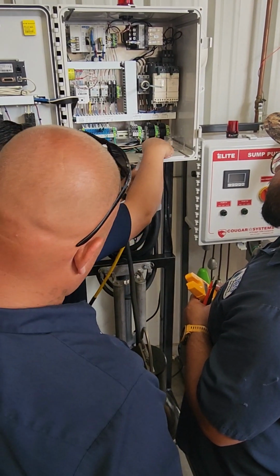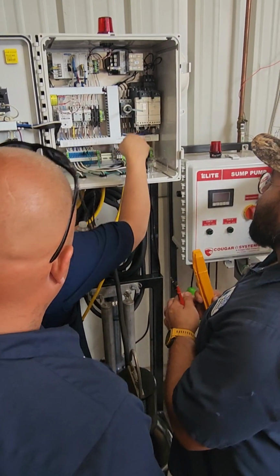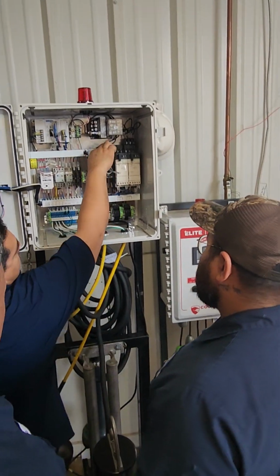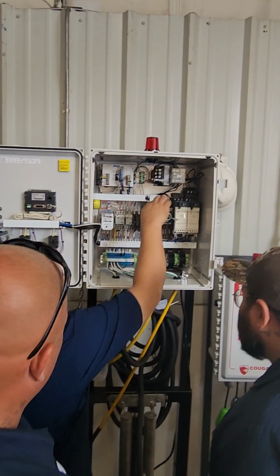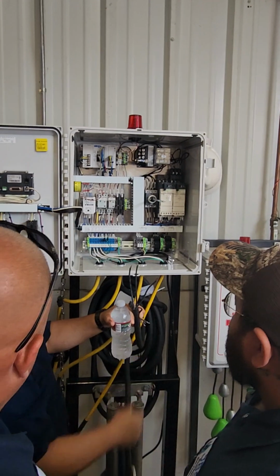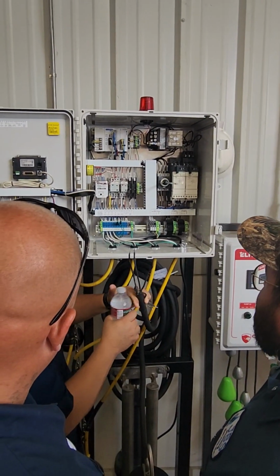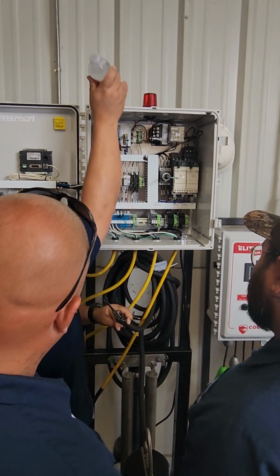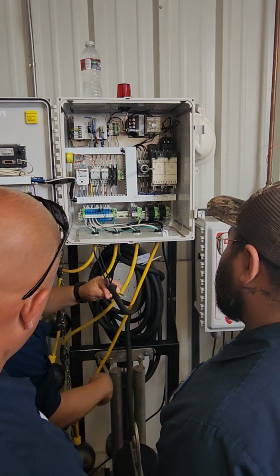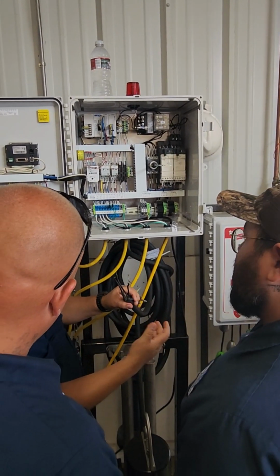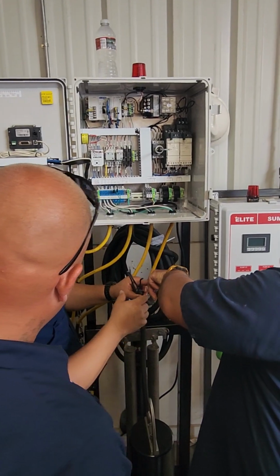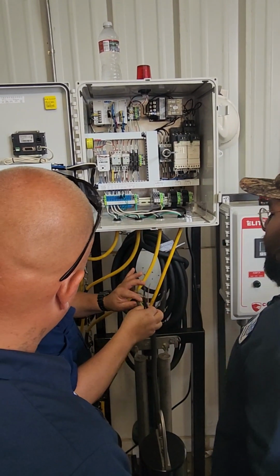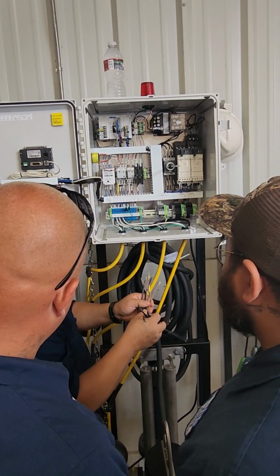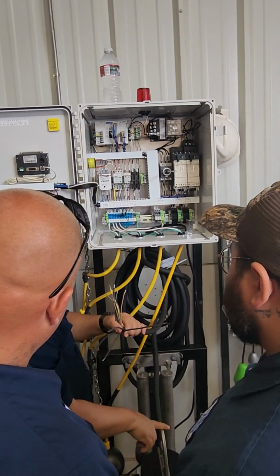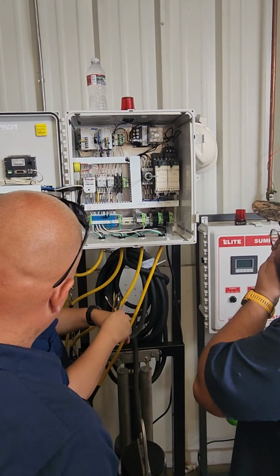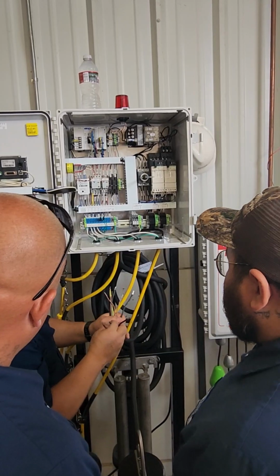You can also check one of your cables of the incoming power, but mostly it's always best to check directly on the black wires. I always have black wire on our pumps, but others have black, red, and white. And these are power right here, right? These are your high temps. This is a dual motor, so it can be 230 or 480. So you will have to do the combination to make it whatever voltage you have.